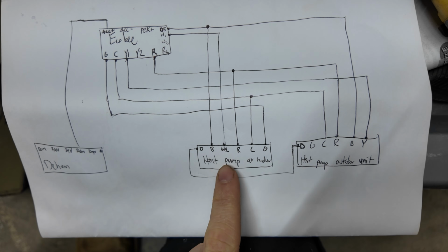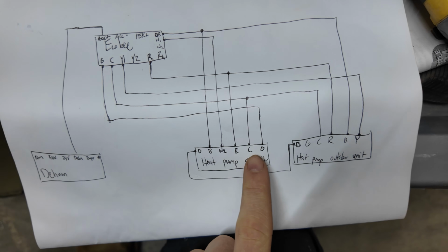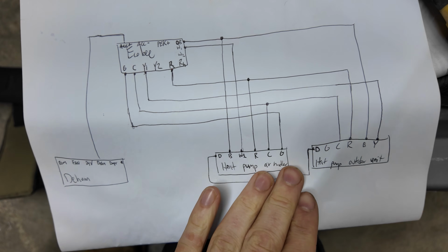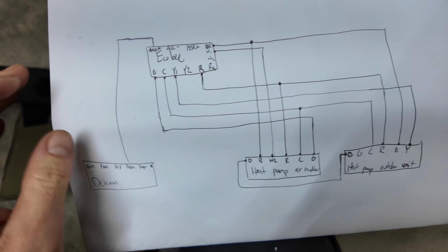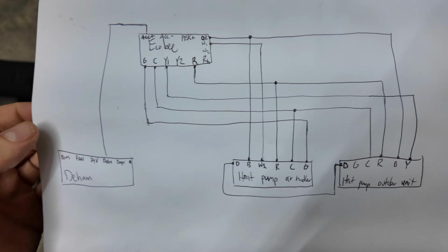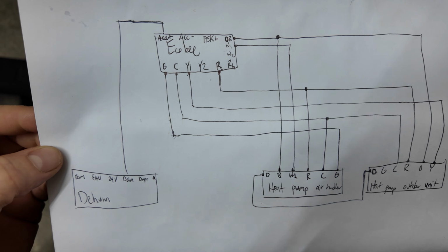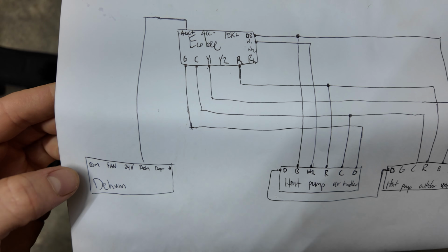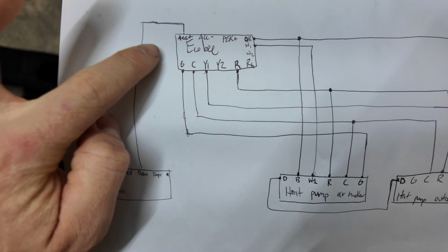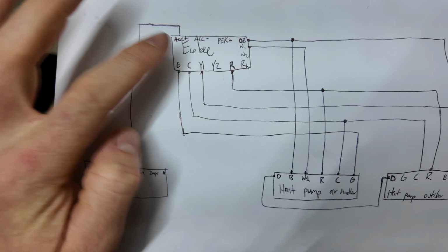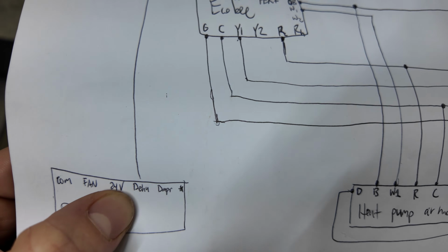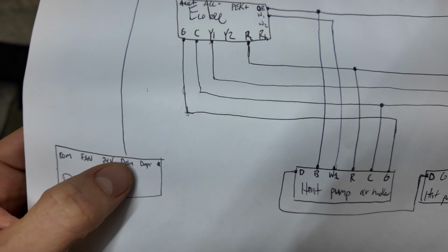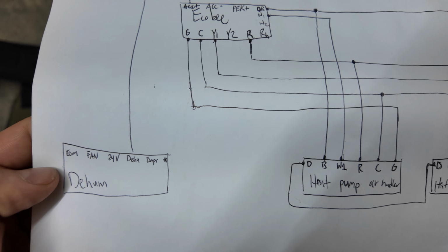And of course it also has to integrate with our Mr. Cool heat pump indoor and outdoor unit. So based on the Mr. Cool instructions, the ecobee instructions, and the dehum instructions, I think I put together my very primitive wiring diagram. And for the dehum, I think I legitimately only need one conductor from the accessory positive outlet of the ecobee down to the dehum outlet of the dehumidifier, which runs both the compressor and the fan at the same time.